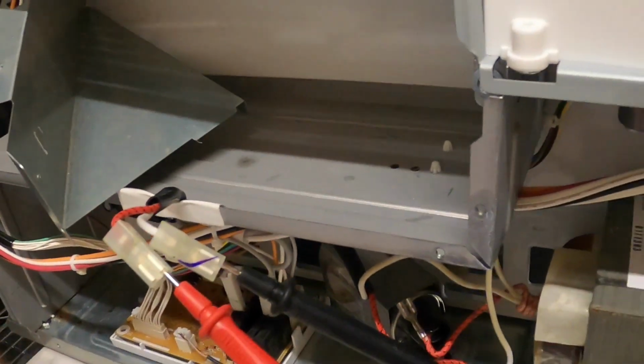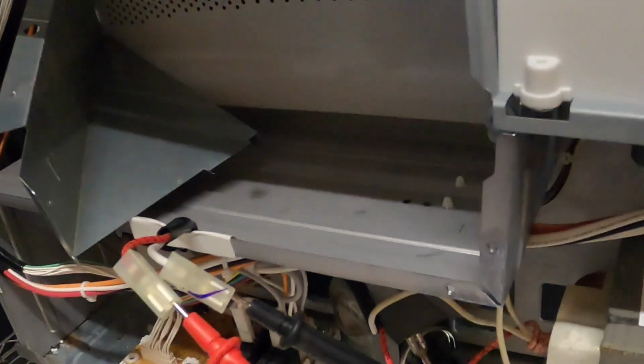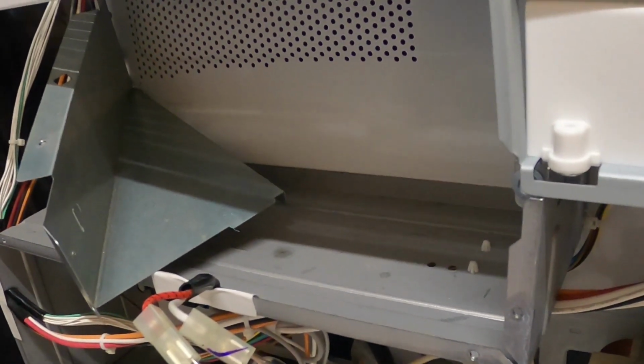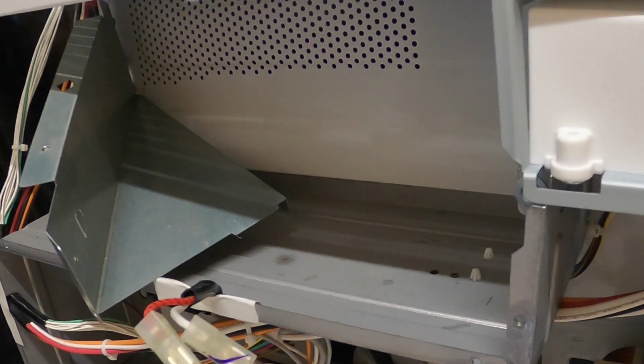So it's very tough to see, and there's no way I can get it on camera with my camera equipment. But there's a hole up in there where you can look and see if that antenna has been burned up. If that waveguide is burnt, the unit is not repairable at all, and you will have to replace the entire microwave. And again, with this model, I've seen it half a dozen times, so it's not unheard of.